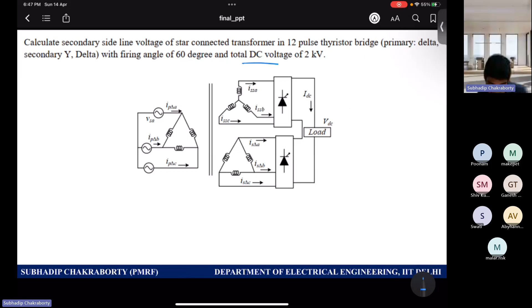So it is again a 12 pulse thyristor based device, and you are given some information that the total DC link voltage is 2 kilovolts and firing angle is 60 degrees, because now it is a thyristor based controlled rectifier. So again, I gave you the information already, that 3 root 2 by pi, V line to line RMS into cos alpha will come now because it is a controlled rectifier, is equal to VDC. But what is VDC for one device? For one device you apply this transformation formula. So VDC by 2 is 1000 volts, which is equal to 3 root 2 by pi V line to line.